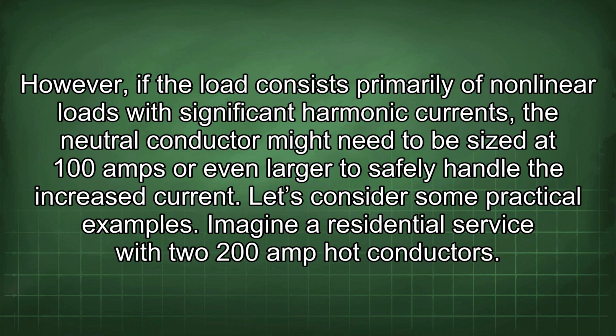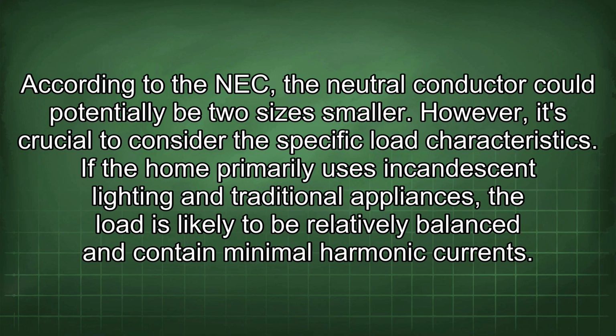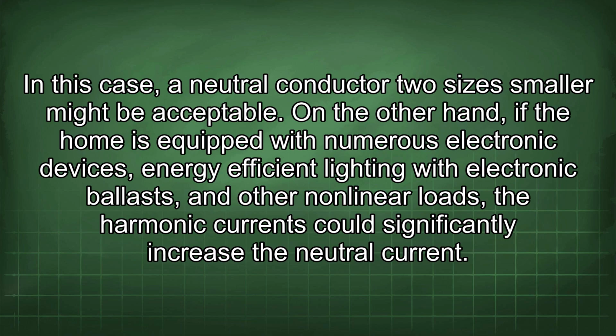Let's consider some practical examples. Imagine a residential service with two 200 amp hot conductors. According to the NEC, the neutral conductor could potentially be 2 sizes smaller. However, it's crucial to consider the specific load characteristics. If the home primarily uses incandescent lighting and traditional appliances, the load is likely to be relatively balanced and contain minimal harmonic currents. In this case, a neutral conductor 2 sizes smaller might be acceptable.